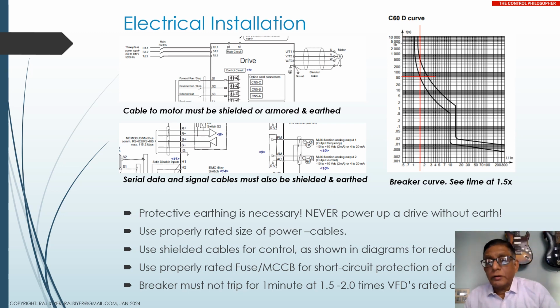Okay, the VFD needs a circuit breaker upstream to protect it from short circuit. We have to look at the circuit breaker tripping curve to select it suitably. What we do is to see the time of tripping at about 1.5 multiples. Let's say that in this case at 1.5 times the rated current, which is on the x-axis of this graph, it will trip at slightly more than 50 seconds. That is actually the 1 minute line, 60 seconds.